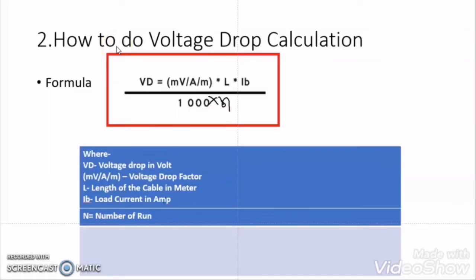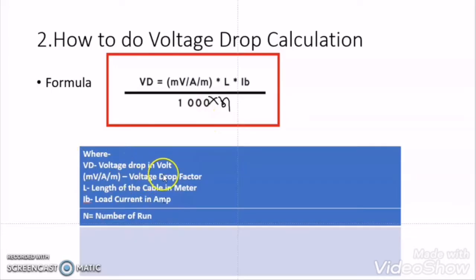So far we understand why to calculate the voltage drop and what is the importance of calculating it. Our second topic in this video is how to calculate the voltage drop. There is a formula: Voltage Drop (Vd) = Vd factor × length of cable (L) × load current (Ib) / (1000 × number of runs (N)). Vd is the voltage drop in volts. This is the voltage drop factor. L is the length of cable in meters. Ib is the load current in amperes. N is the number of runs.